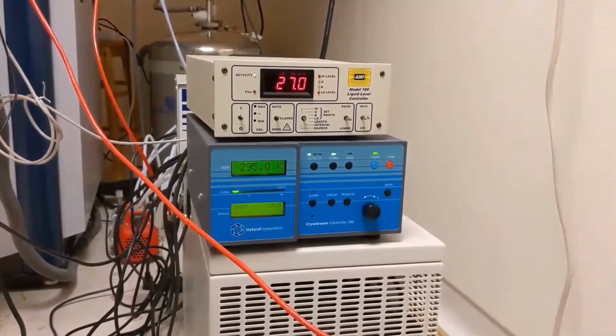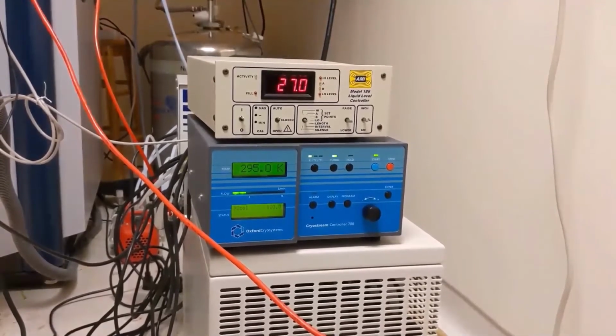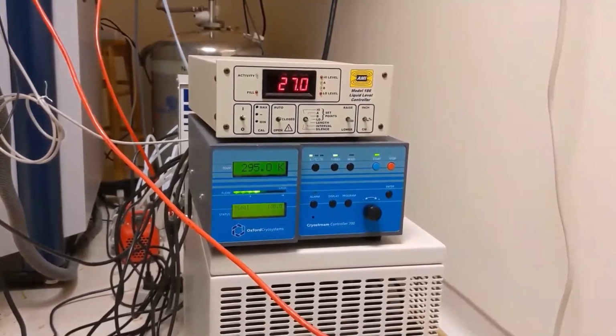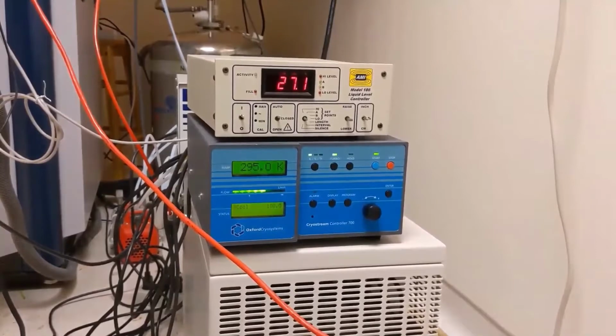The top temp screen now displays the current temperature. It will take approximately 20 minutes to go from room temp to 100K. Most of the time, it will already be at 100K and you'll be able to skip this step.